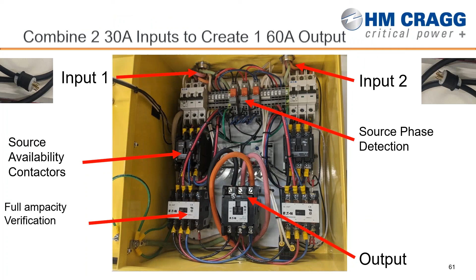We've got the input protection for input 1 and input 2, both 30 amp input circuits. We also have the source phase detection relays, which check phase A, B, C off of each source to make sure they're both in a clockwise rotation and all matching. This is a precautionary step before we bring the inputs to a main junction point within the box.